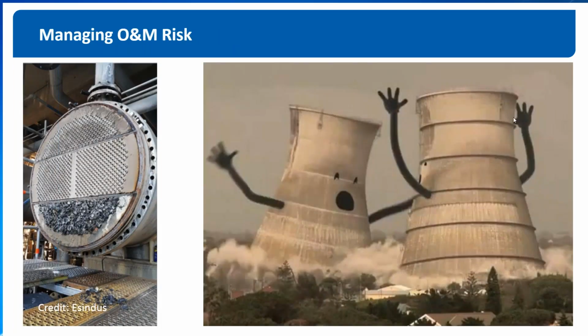CapEx investments for operations and maintenance savings are not always at the top of the priority list at industrial sites, but for cooling towers, there is a good chance to reduce risk and save money with small investments. Obviously, the biggest risk is collapsed fill. Normally, it doesn't go from the outside, but it will almost certainly have a big impact on your production.